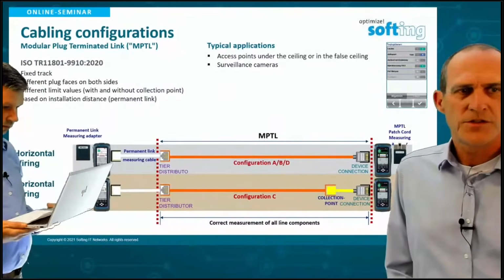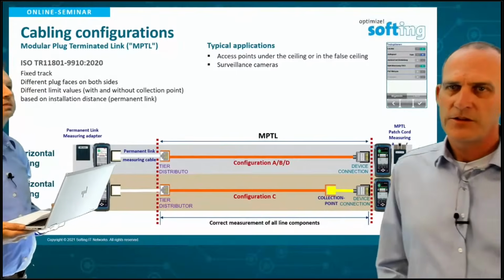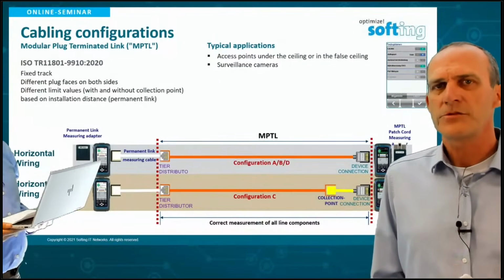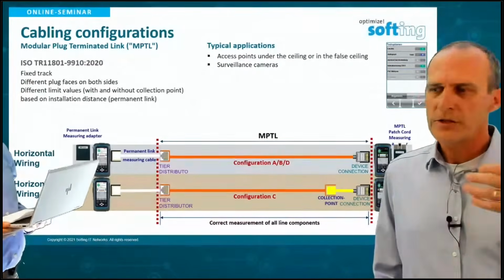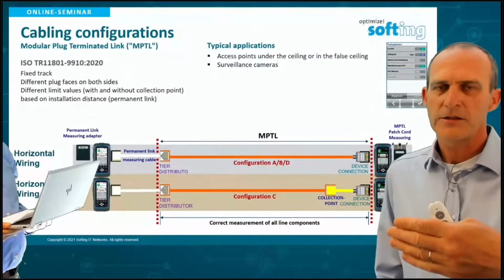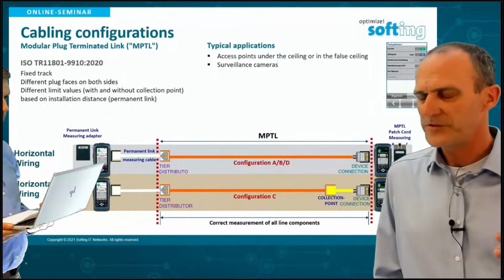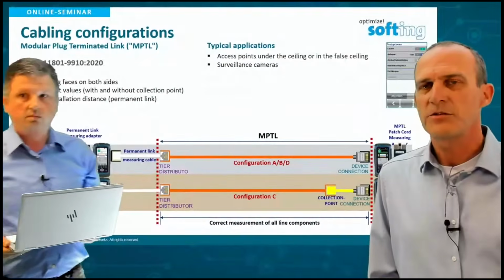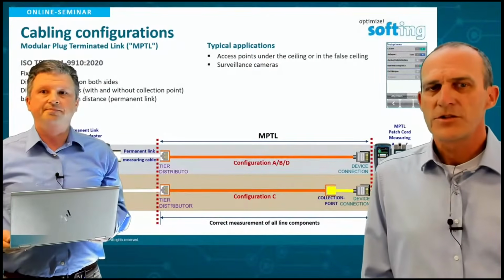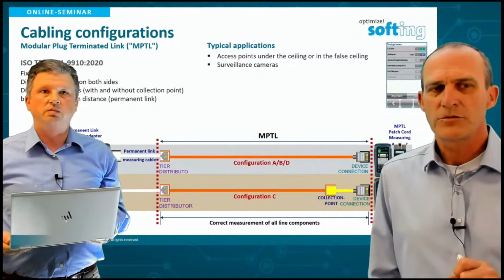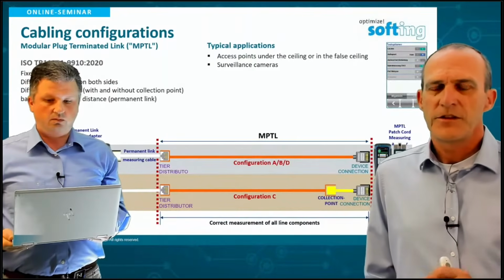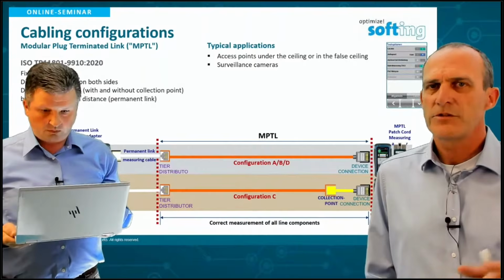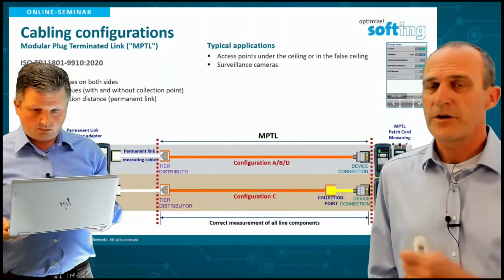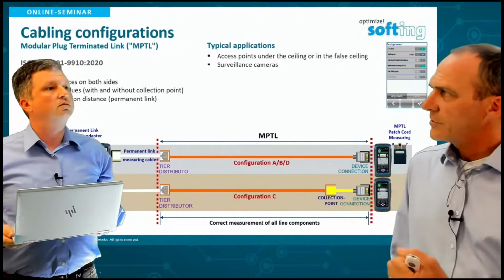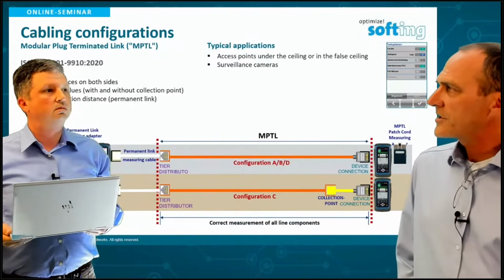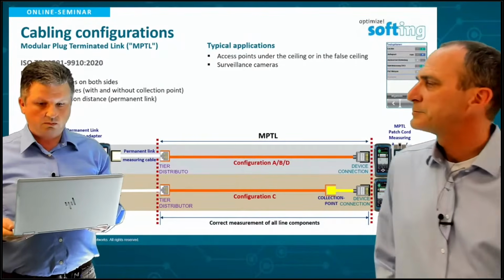We recommend using the locator function in the testers. With the crosstalk and return loss locators, you can locate along the link after how many meters you're going to have a fault. That's perfect to discriminate whether it's the consolidation point, the end of the link, or maybe somewhere else - if you pull too hard you might also damage the cable and get return loss errors along the cable.